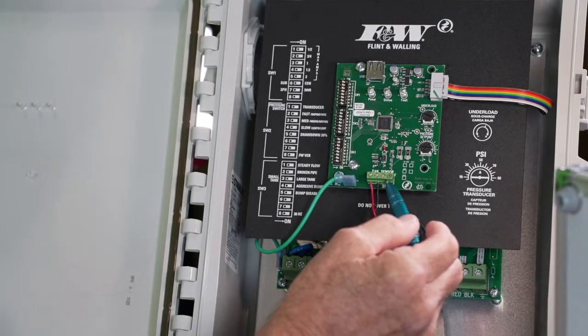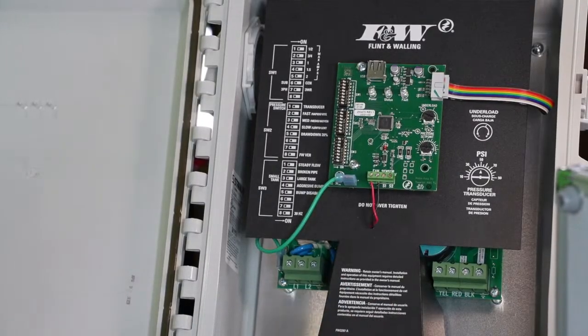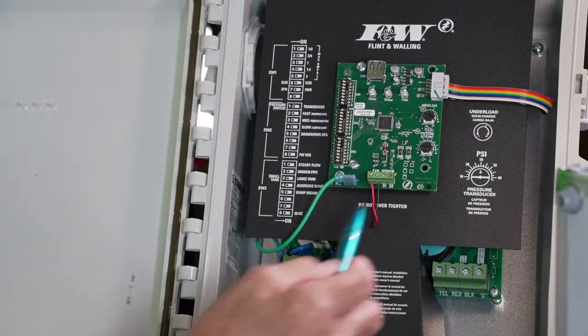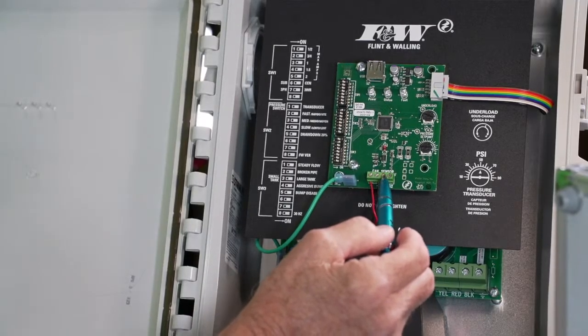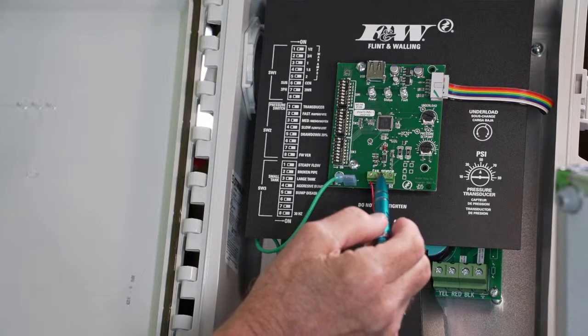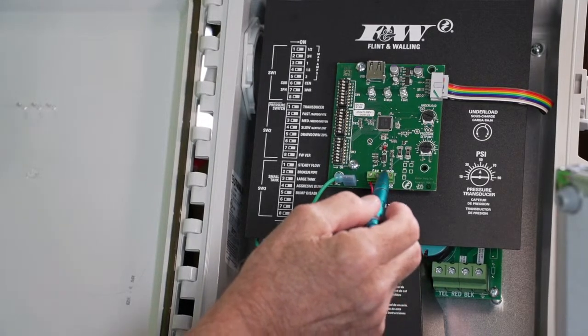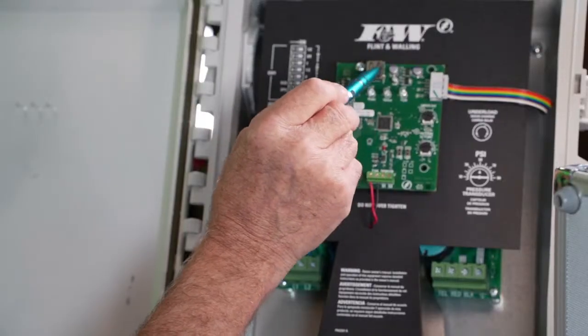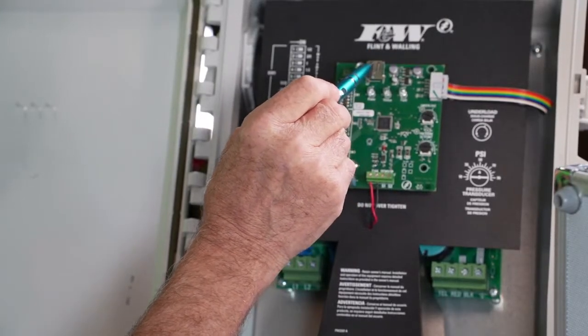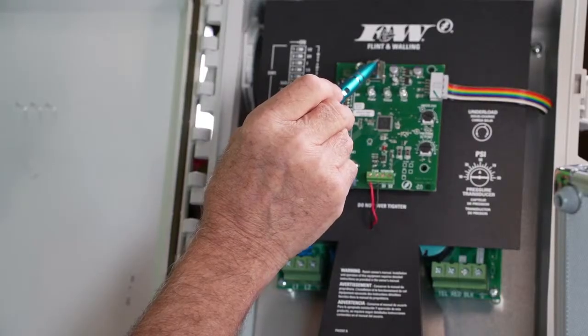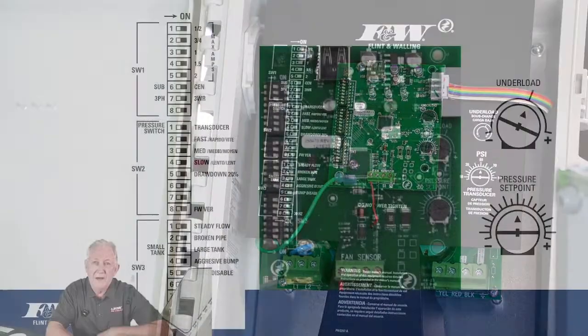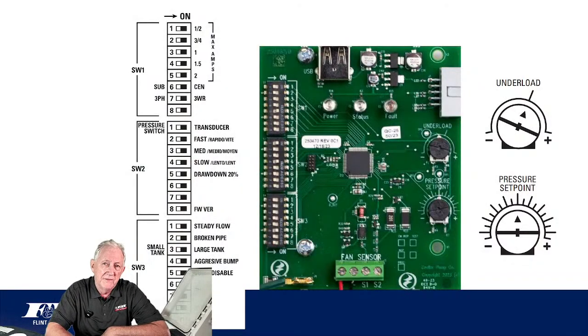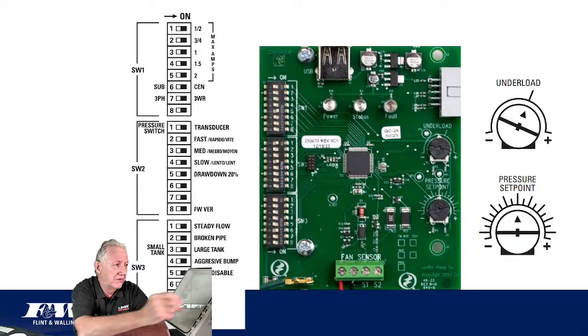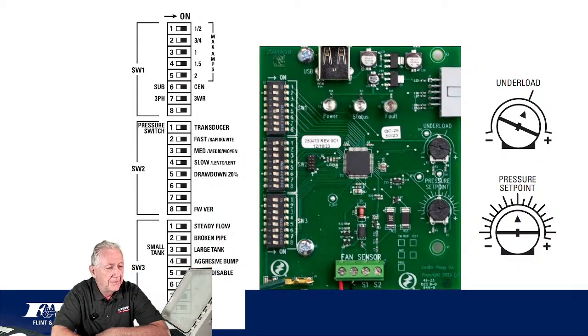These other 2 terminals is where you're going to be wiring in whatever type of device we're going to use to run this drive, be it a switch or a transducer. All right, those will get wired right in here, and I'm going to circle back on both those in a bit. The other thing that I would point out about the drive is up here at the top is a USB port, and this is really a great idea, so that this drive can be updated remotely in the field with just a flash stick. All right, so right there is the USB port where that would go.